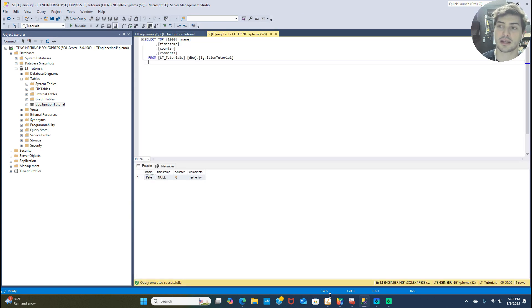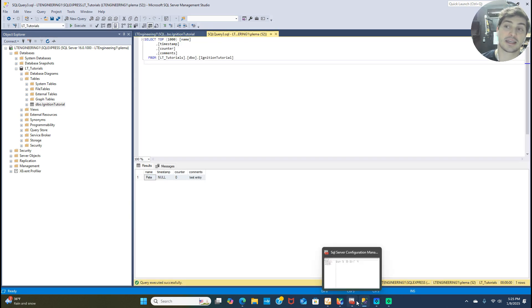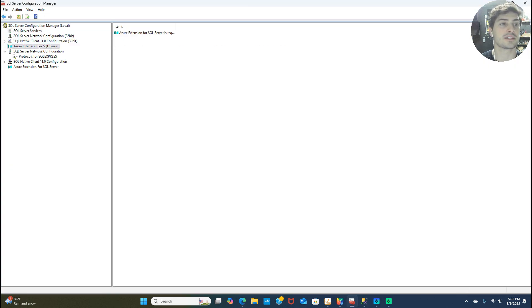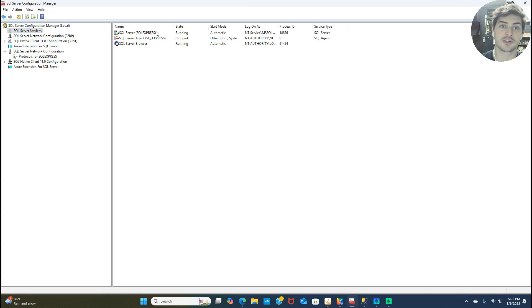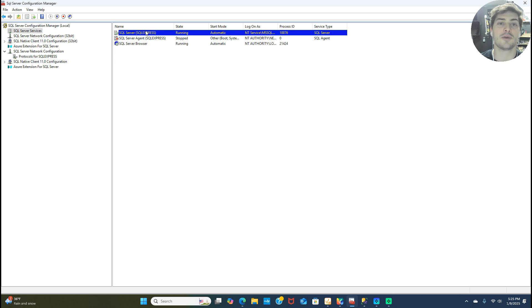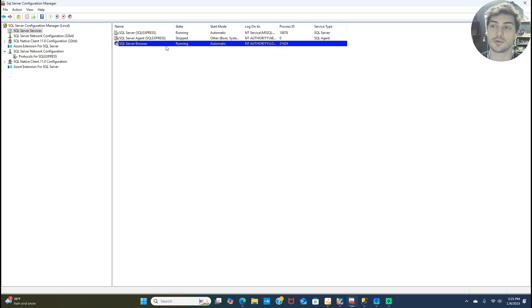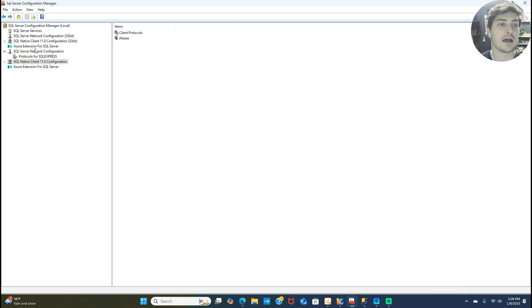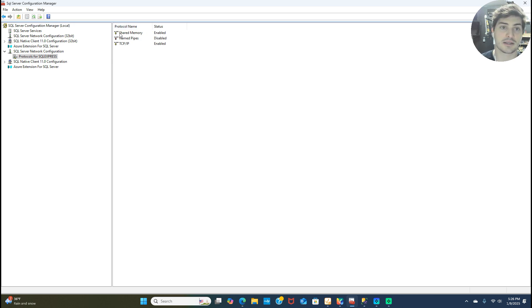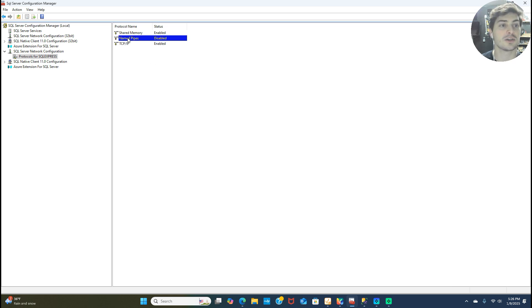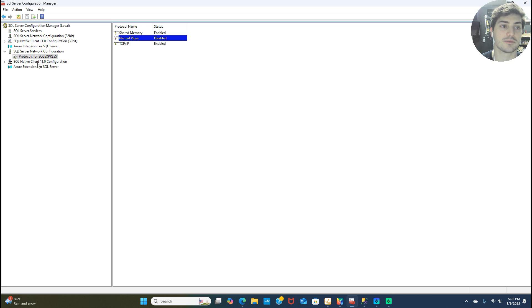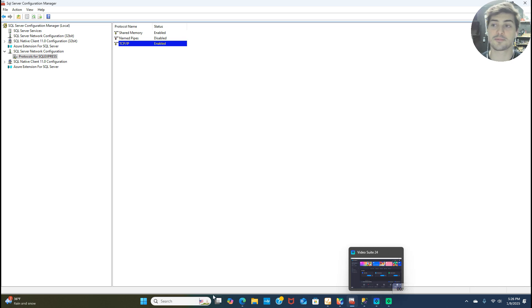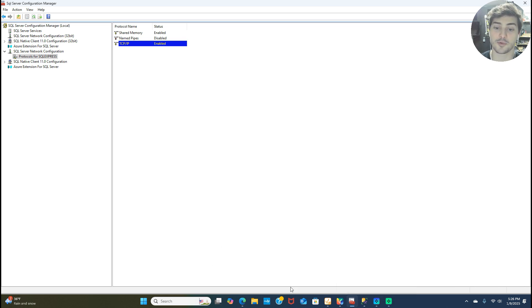The part that I want to stress before you even get to Ignition is you need to make sure from the SQL Server Configuration Manager that you have SQL Server running and SQL Server browser running, or your gateway instance will not be able to connect to it. And then the only other thing I think is worth discussing here: Ignition is a web hosted TCP/IP based tool when it connects to databases. So you want to make sure, again, from the SQL Server Configuration Manager that the TCP/IP service is enabled. That is all pre-reqs before we do any piece from Ignition.